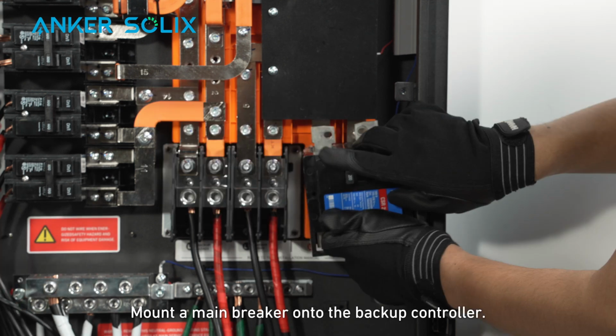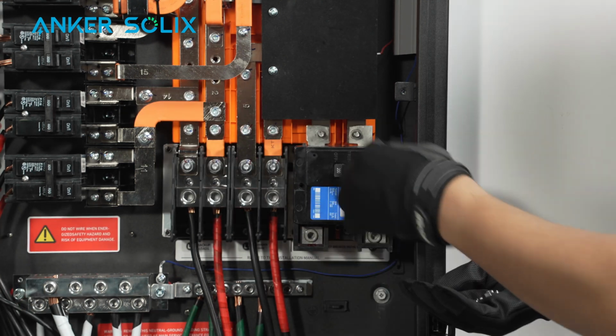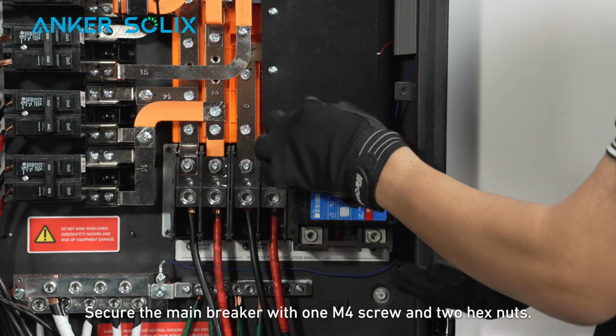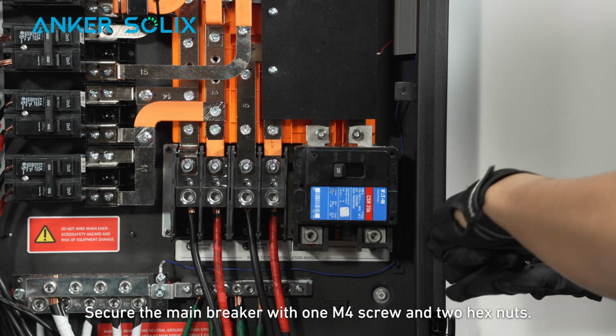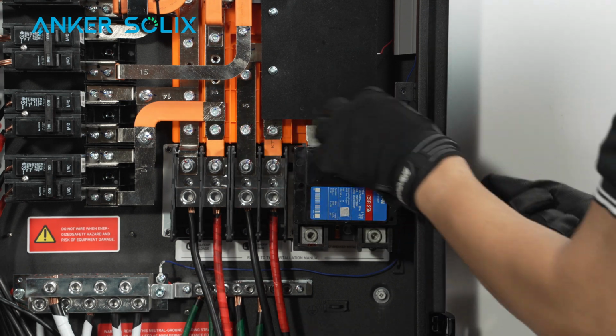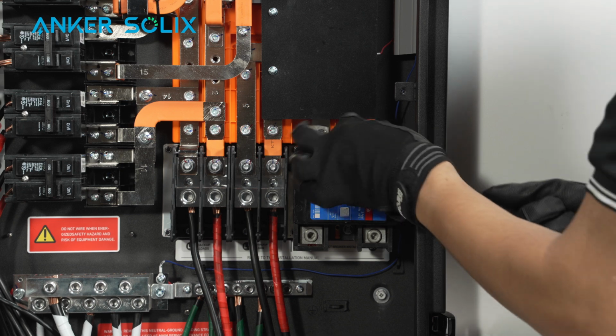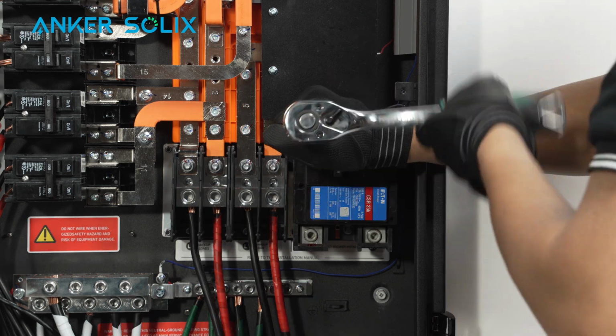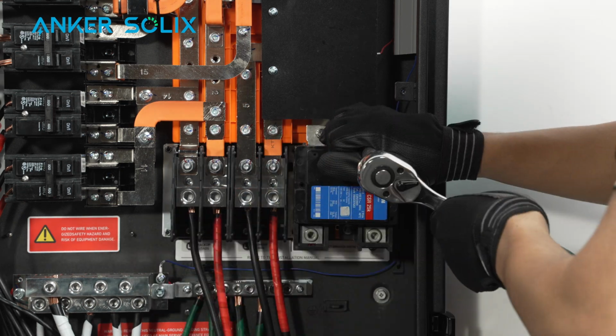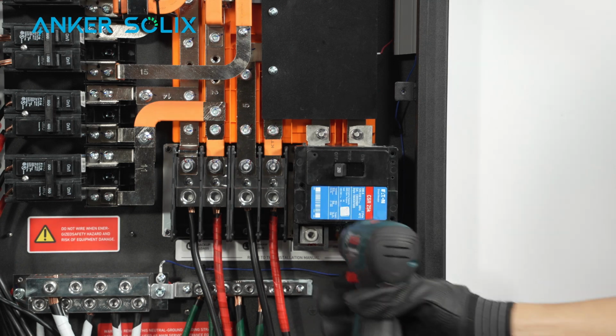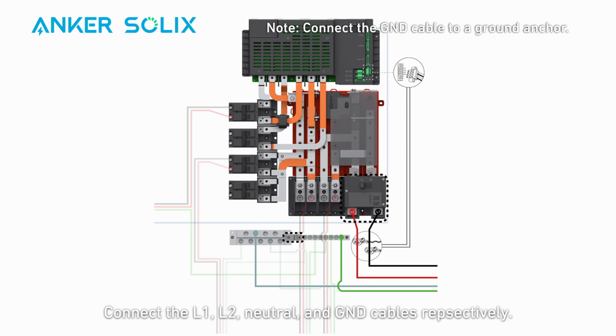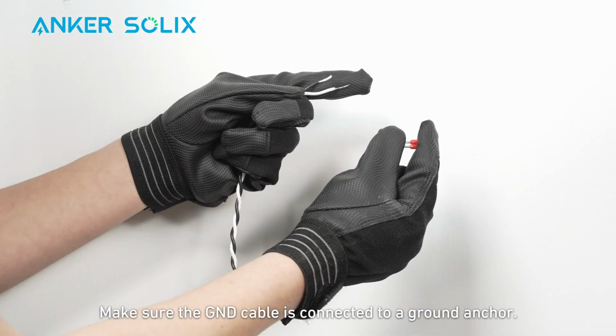Mount a main breaker onto the backup controller. Secure the main breaker with one M4 screw and two hex nuts. Connect the L1, L2, neutral, and ground cables respectively. Make sure the ground cable is connected to a ground anchor.